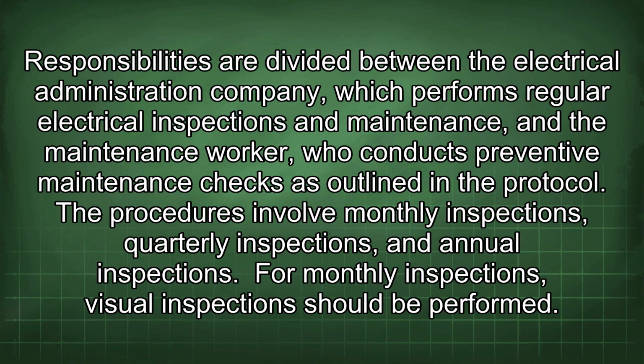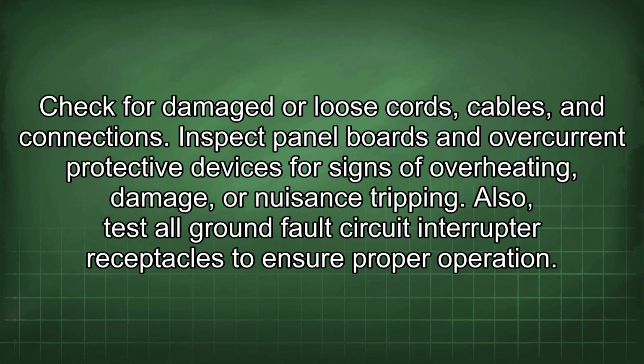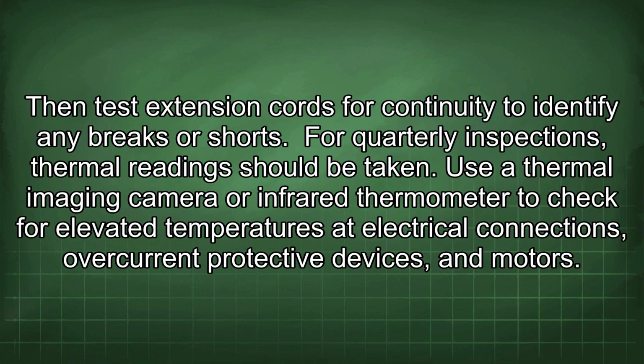The procedures involve monthly inspections, quarterly inspections, and annual inspections. For monthly inspections, visual inspection should be performed. Check for damaged or loose cords, cables, and connections. Inspect panel boards and overcurrent protective devices for signs of overheating, damage, or nuisance tripping. Also, test all ground fault circuit interrupter receptacles to ensure proper operation. Then test extension cords for continuity to identify any breaks or shorts.